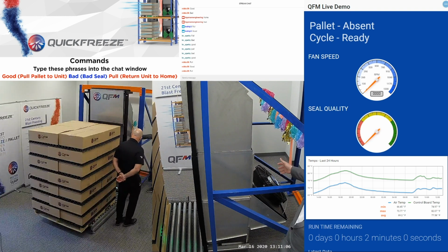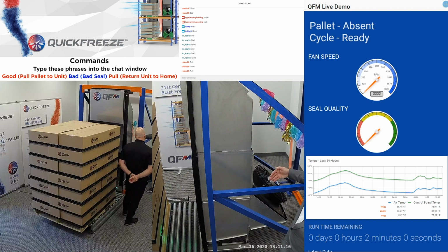But that's the only power that's required for the QFM. So that goes into the fan, which is an EC, electrically commutated motor, and from the motor we power the controls. And with the controls we are constantly sensing the position of the pallet that's in front of it so that we can turn it on and turn it off automatically when the pallet's put in and put away. And we're measuring the temperature and the pressure inside the plenum so that we can do a good seal check.